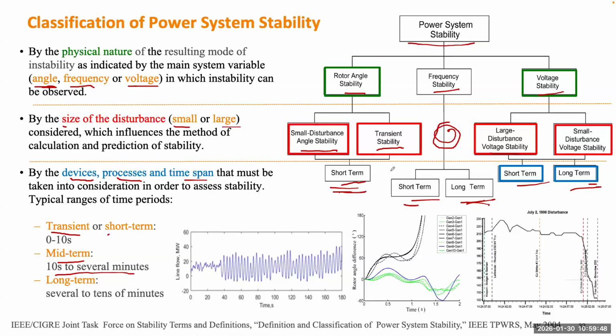The bottom figure gives you some examples. The first one indicates the line flow of a power system is oscillating. It starts from this time, and you see the envelope stays about the same, at least not decaying, which means the system has sustained oscillations. So damping can be either negative or very small, not large enough. This is a typical example of small disturbance angle stability.